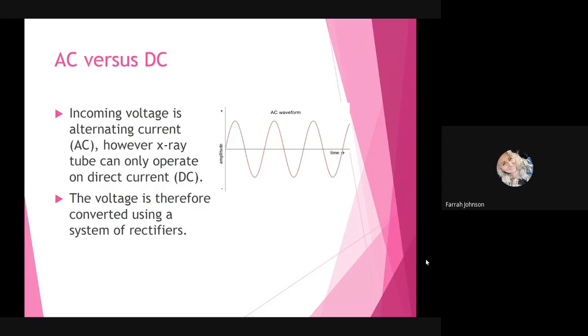So then that brings us to alternating current versus direct current. So incoming voltage is going to be alternating, meaning that the waveform swings in a positive direction above the midline and then again into the negative portion of the waveform. Okay, so that's what is considered alternating. However, note that the X-ray tube can only operate on direct current. Okay, so the voltage is therefore converted using a system of rectifiers. So basically, we don't want this varying waveform. We only want a waveform that is on the positive aspect of this wave. So basically, what rectifiers do is they take these negative portions here and they move them onto the positive half cycle, which we'll talk about more here on the next slide.